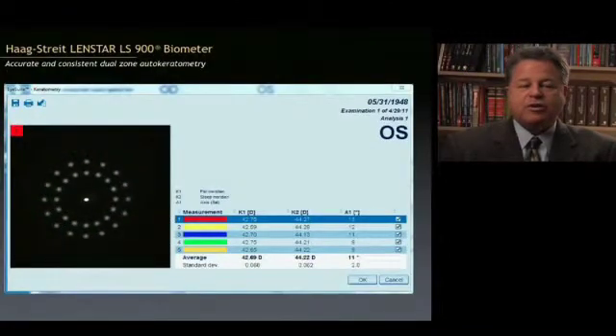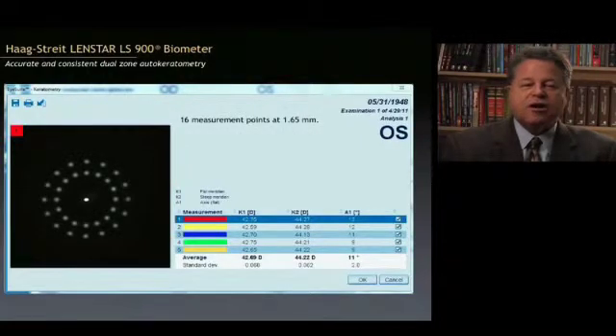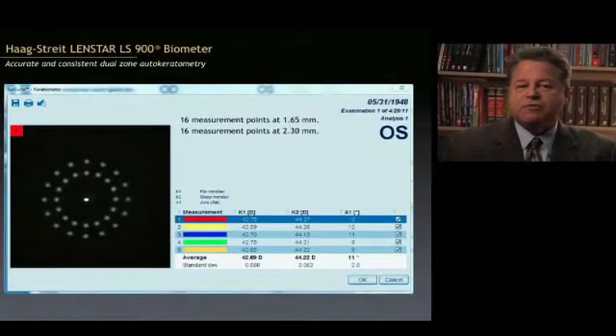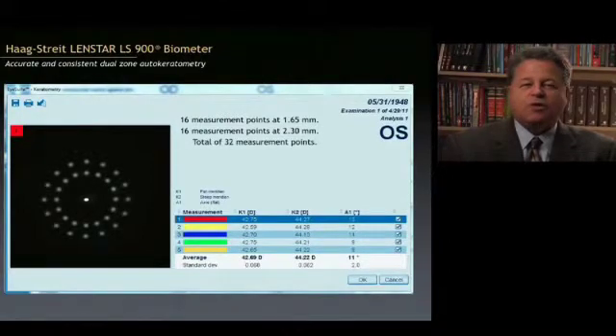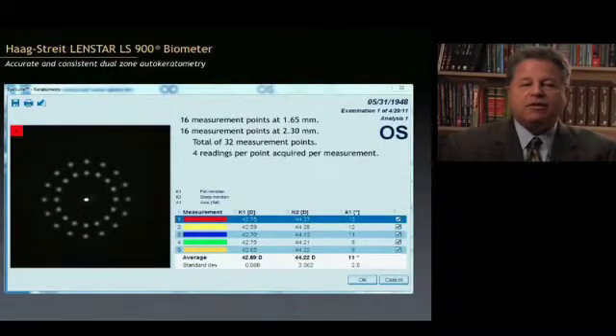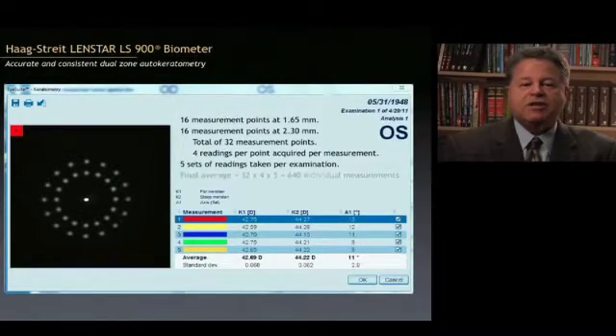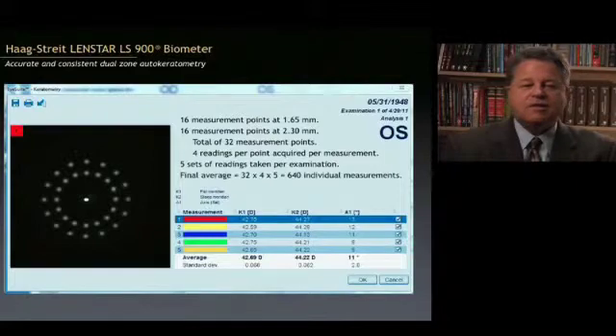The keratometry is really one of my favorite aspects of the LenStar. It has a combination of a 1.65 and 2.3 mm set of zones, and at each zone it measures 16 points — a total of 32 measurement points. Each time you hit the button it's four readings per acquisition of data. To complete the measurement process you do five sets of readings per total examination, giving us 640 total measurements for your keratometry.